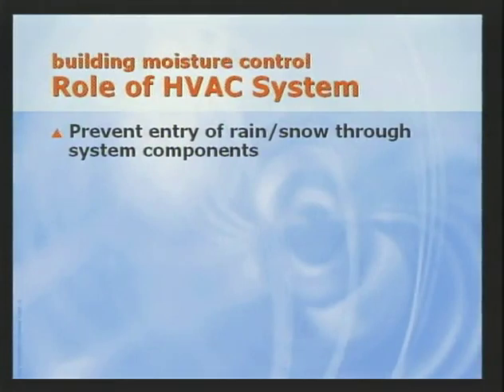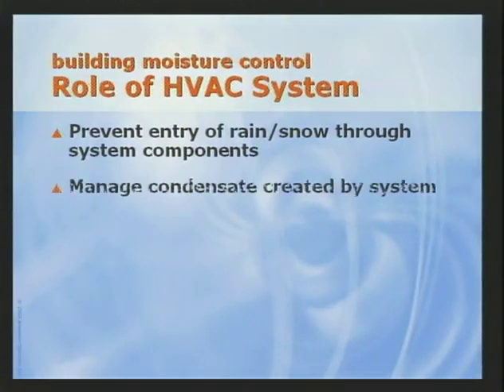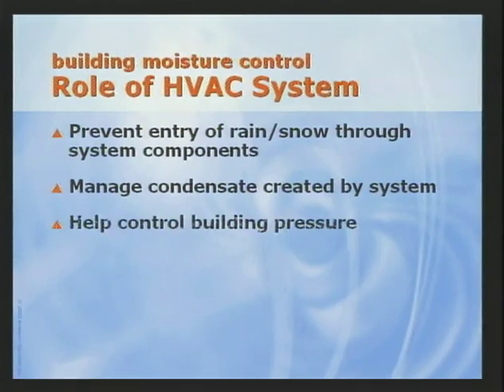Now, specifically, it can prevent rain or snow from entering through the outdoor air intakes or from leaking through equipment or casing or roof curbs. Second, it can help manage the condensate created intentionally at the cooling coil. Third, it can help control the indoor to outdoor pressure difference. And finally, it can help limit indoor humidity levels. For today's broadcast, I'm going to focus on just one of these issues, limiting indoor humidity levels. Now, although many of today's HVAC systems can adequately control the indoor dry bulb temperature, several of them allow the indoor humidity levels to rise, especially during part load operation.